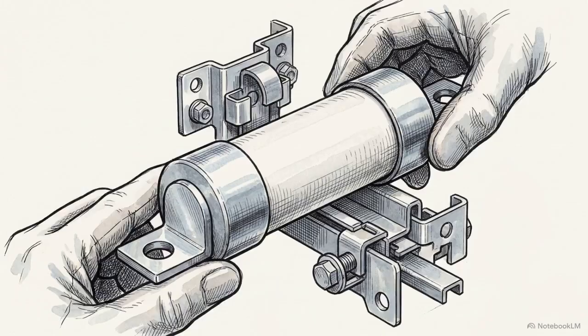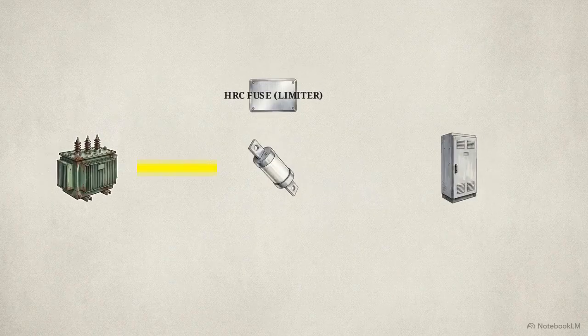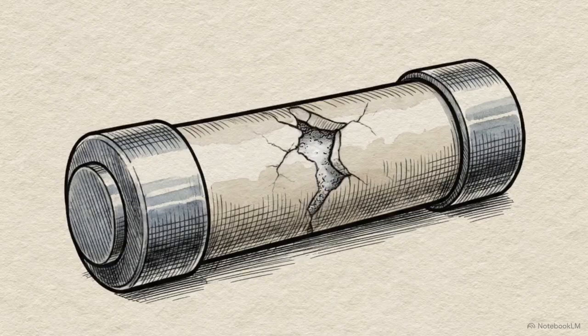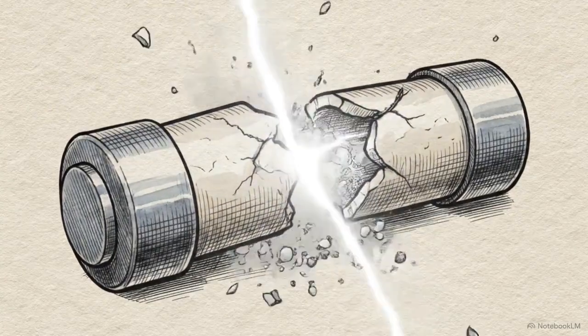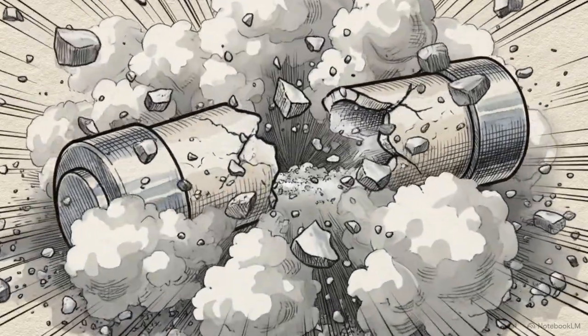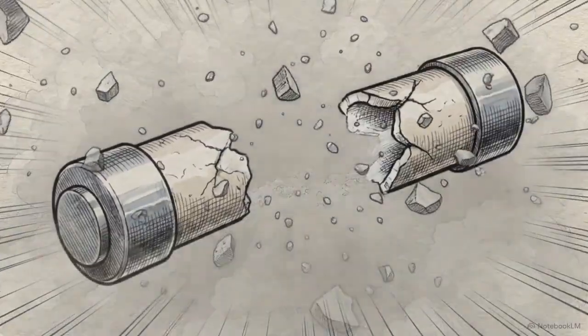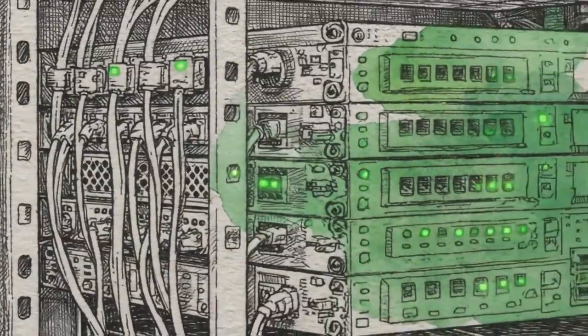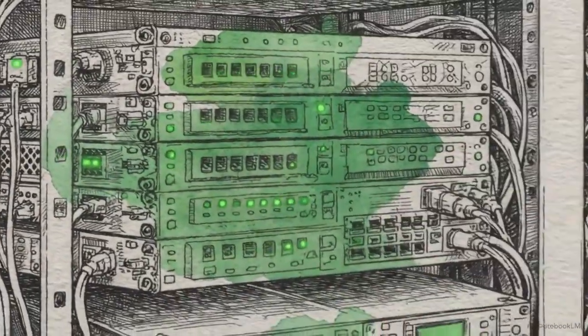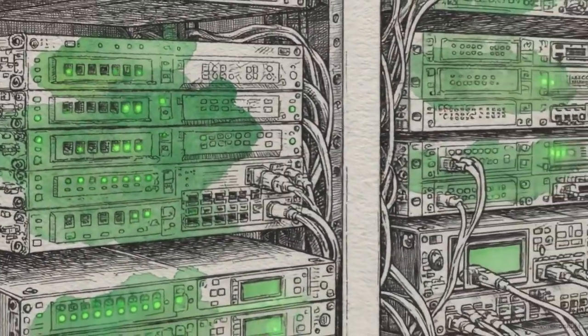In these scenarios, engineers install active fault current limiters, such as precisely rated HRC fuses, placing them upstream to artificially bottleneck the incoming energy. Instead of an entire switchboard exploding, a specialized ceramic fuse violently shatters inside a controlled casing, instantly killing the electrical arc. These limiters successfully cap instantaneous fault currents to a predetermined threshold that the downstream hardware can safely absorb.